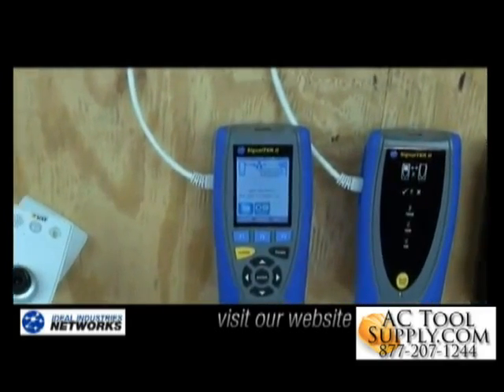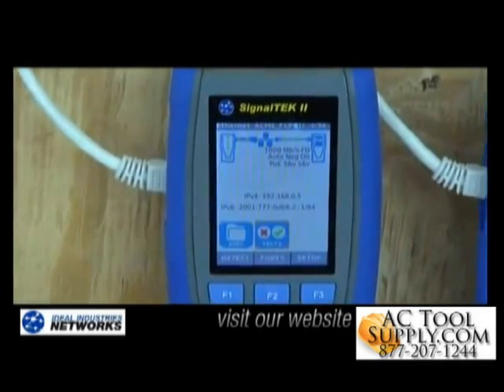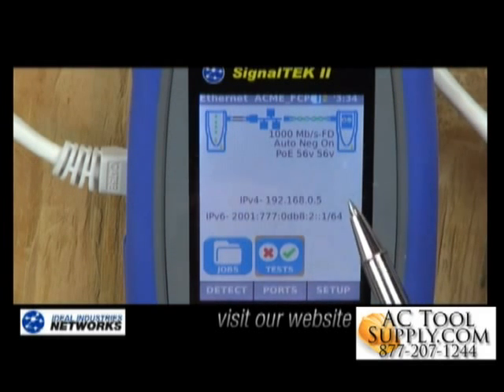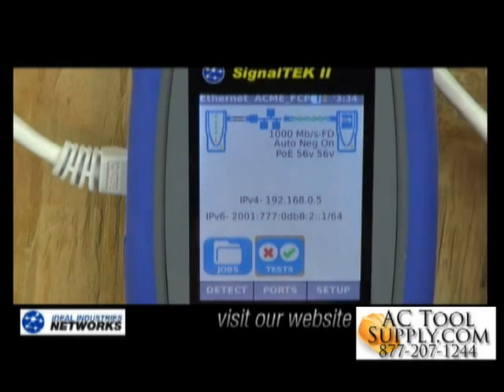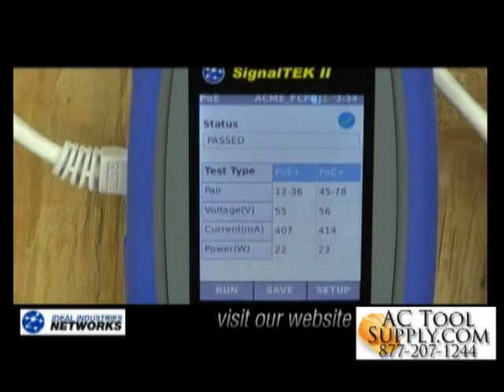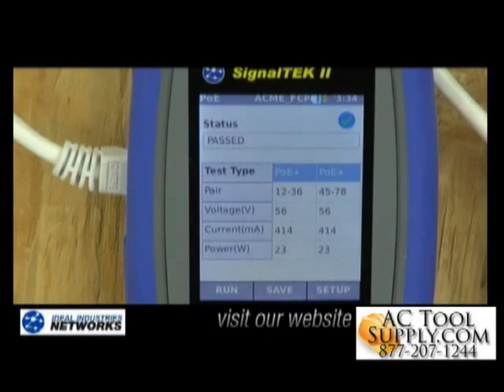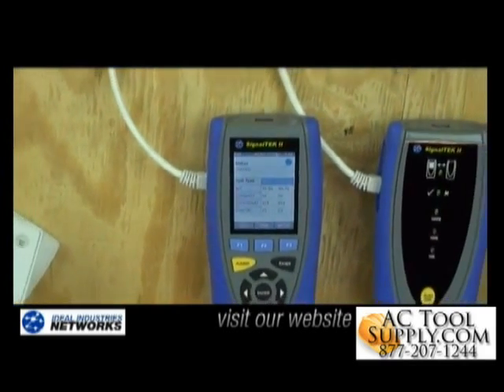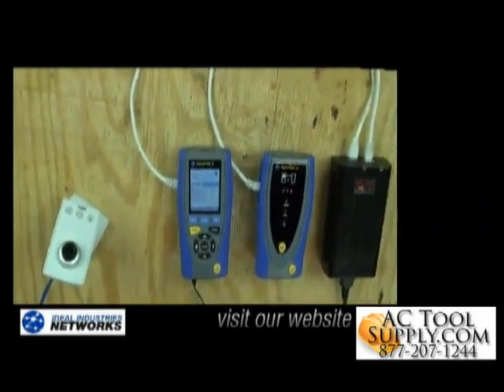Here's a close-up of the Signal Tech 2 Tester. Power over Ethernet is now really commonplace, and testing and troubleshooting it can sometimes be a little bit of a challenge. The Signal Tech 2 can help in a couple of different ways. First, on the home screen, you'll know if PoE is even available because it shows it to you right there on the screen. Additionally, you can test that PoE source to determine how much power is actually available, which is critical in making sure the PoE device is going to work. I'll run a load test — you can see that the PoE injector I'm connected to shows me which pairs PoE is available on, the voltage level, the current in milliamps, and how many watts are available. I can test at the end of a long cable to make sure enough power is getting to my PoE device.